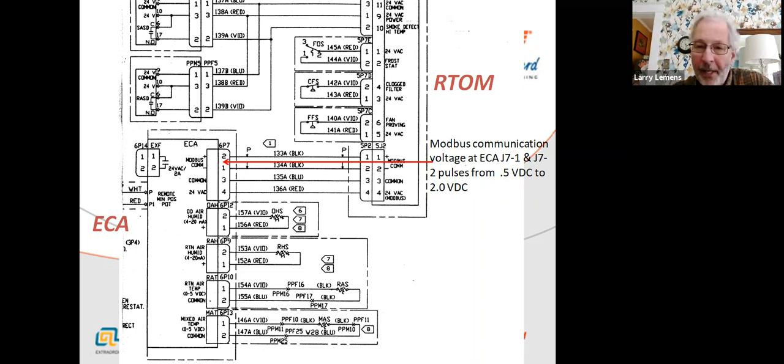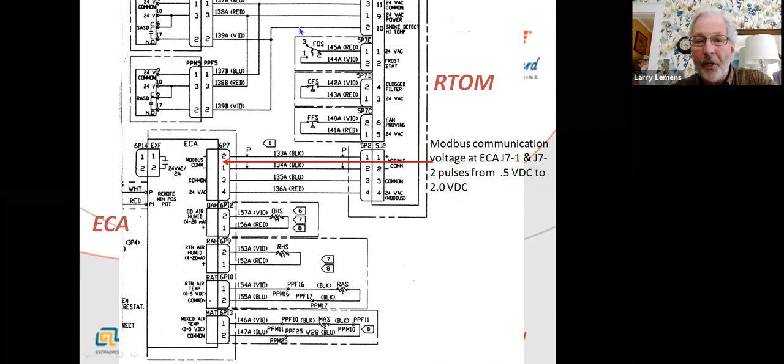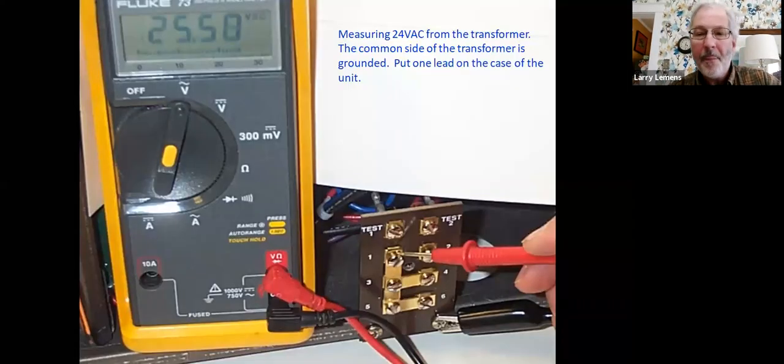Usually on J7 on the options module, if the smoke detector is tripped or the frost stat is tripped, if you just simply unplug them and open that circuit back up again, the unit will start running and take off, and everything is fine. So just remember, we do it a little backwards on ours. These are normally open circuits that close. The airflow switches and clog filter switches are normally closed, but the smoke detector and the frost stats are normally open, so a little different. So keep that in the back of your mind when you're working on these systems.